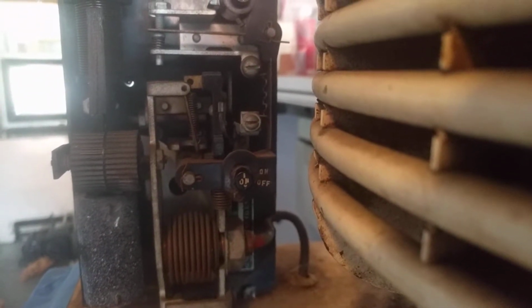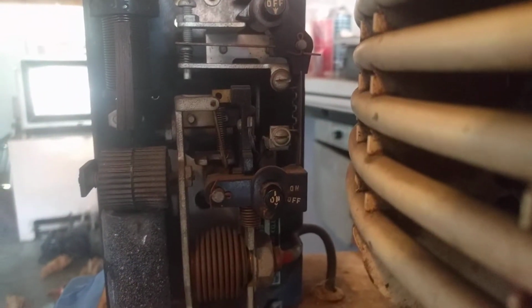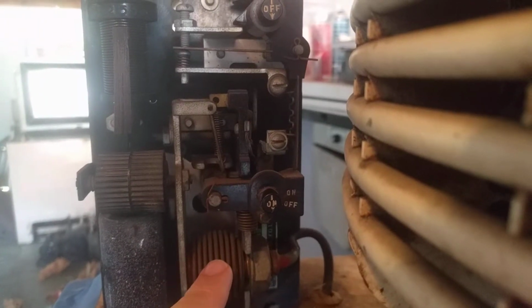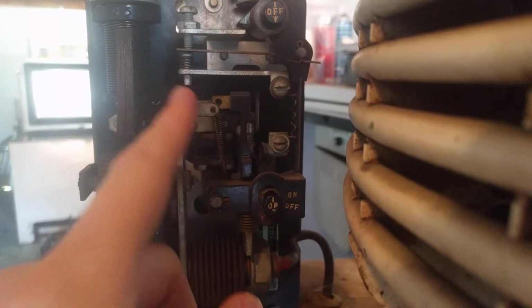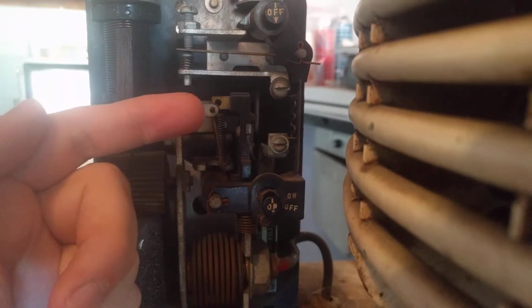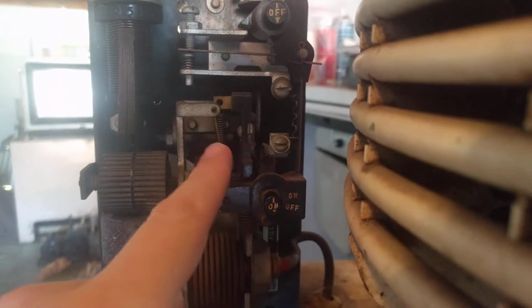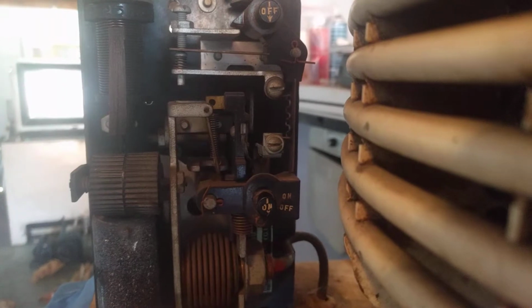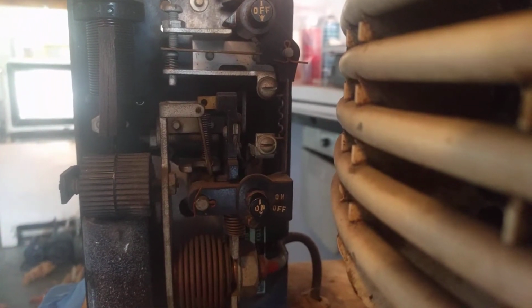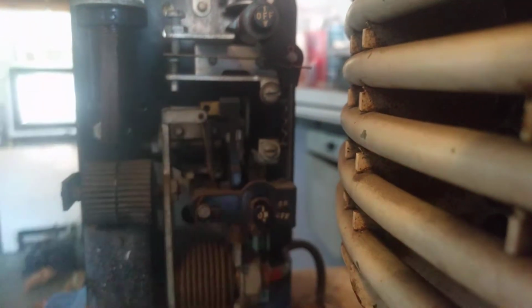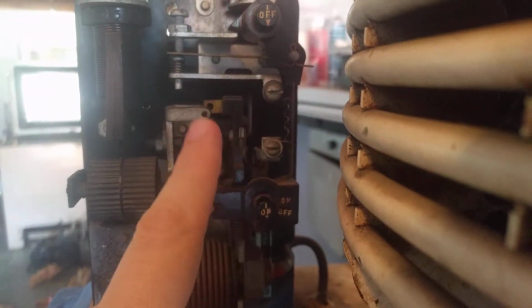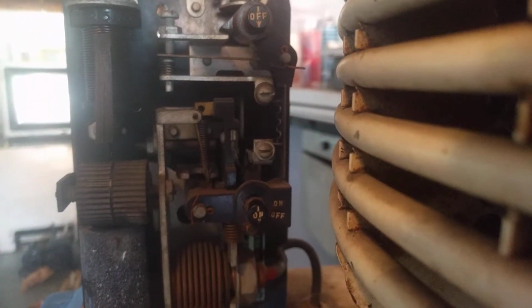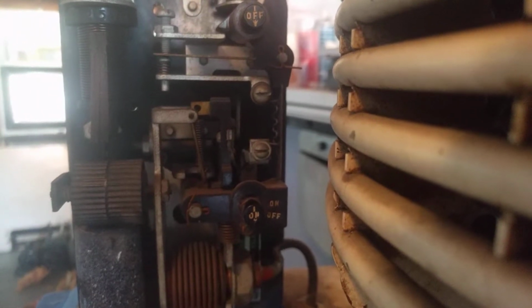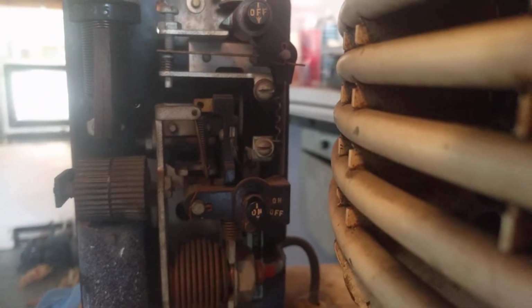Normally, the cycles are on for an hour and off for two hours. However, looking at the contacts here, you can see when the bellows shrinks, this little arm moves, and there is a latch mechanism that will cause the contacts to snap once this reaches the right position. This little piece of metal tends to be approximately vertical when it's just about to trip.